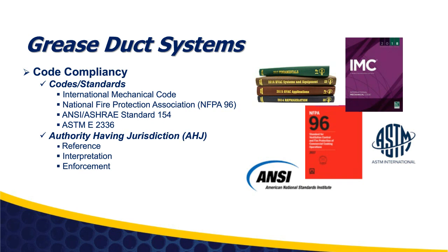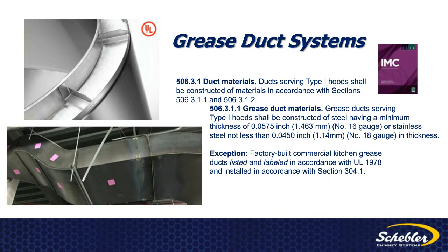So let's look real quick at International Mechanical Code and see what's in there about duct construction. So it's basically going to state again, duct serving type 1 hoods need to be built in accordance with section 506.3.1.1. And in that section, basically, they're going to dictate what gauge and type material is going to be acceptable. So for field fabricated grease duct, it can be of carbon steel, a minimum of 16 gauge material can be utilized. And if the contractor or engineer specifies stainless steel, 18 gauge would be the minimum thickness that could be applied. Now, the exception to those gauge materials is to utilize a factory-built commercial kitchen grease duct product that is listed and labeled in accordance with UL 1978. And we'll definitely hit on that UL listing later on.